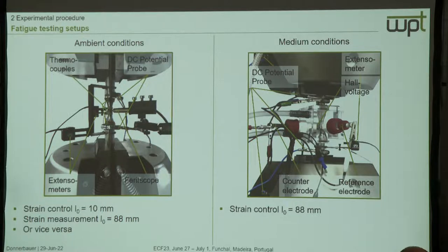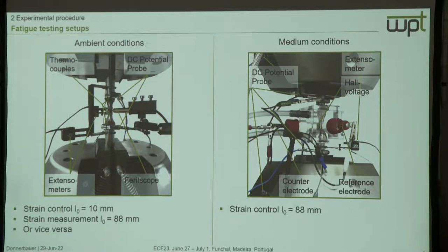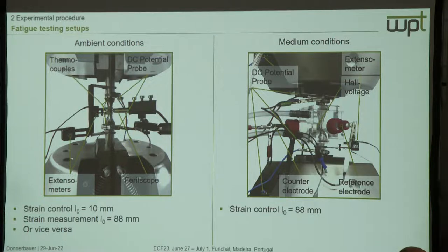Both extensometers were used to control tests. For the medium testing setup, the 10 mm gauge length extensometer has to be removed since there is a PMMA cell around the specimen, which has an inlet and outlet for electrolyte — always fresh electrolyte around the specimen. This allows us to have a standard three-electrode setup: reference electrode, counter electrode, and the specimen itself as the working electrode, so we can track open circuit potential during the test.